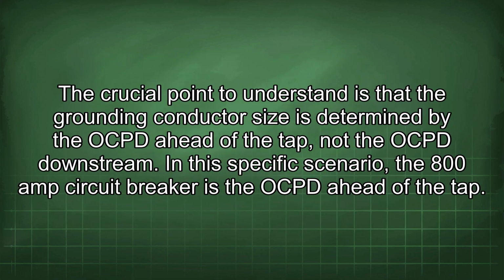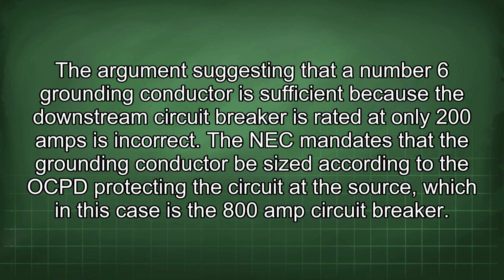The crucial point to understand is that the grounding conductor size is determined by the OCPD ahead of the tap, not the OCPD downstream. In this specific scenario, the 800 amp circuit breaker is the OCPD ahead of the tap. The argument suggesting that a number 6 grounding conductor is sufficient because the downstream circuit breaker is rated at only 200 amps is incorrect. The NEC mandates that the grounding conductor be sized according to the OCPD protecting the circuit at the source, which in this case is the 800 amp circuit breaker.